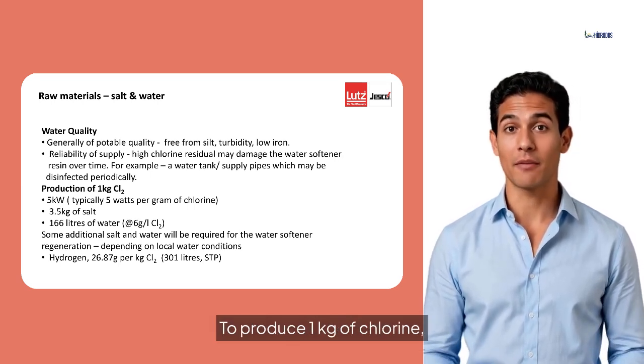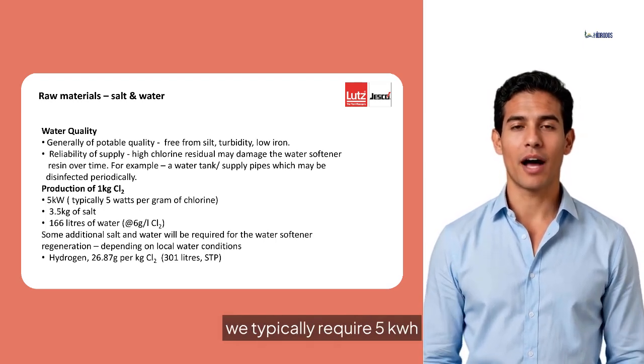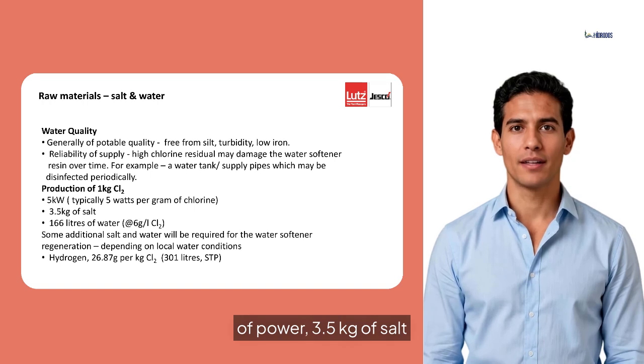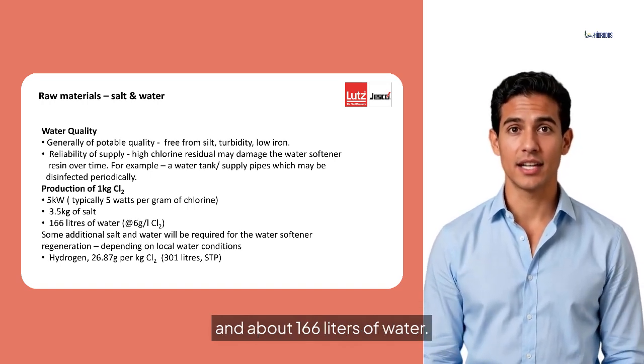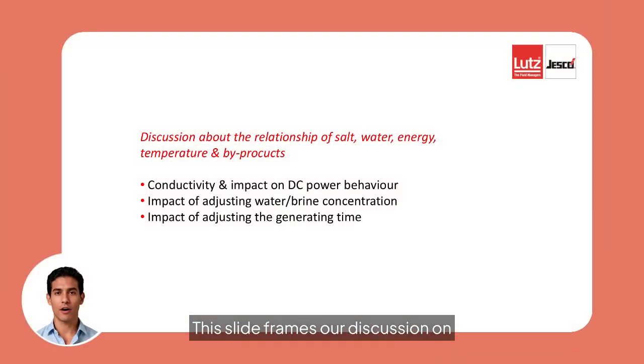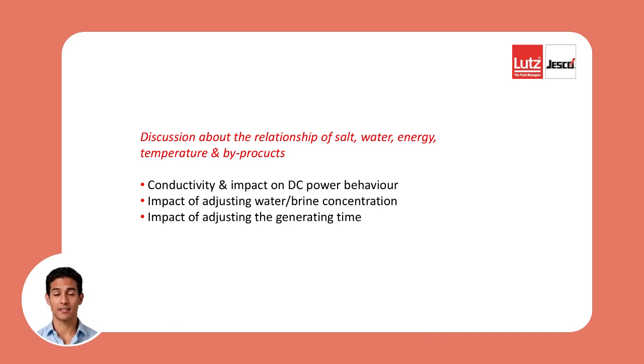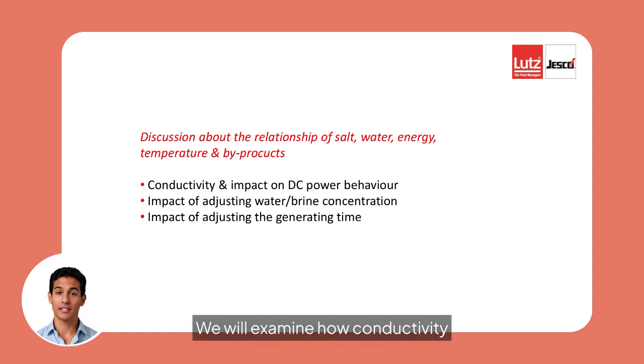To produce 1 kilogram of chlorine, we typically require 5 kilowatt-hours of power, 3.5 kilograms of salt, and about 166 liters of water. This slide frames our discussion on how salt, water, energy, temperature, and byproducts interact. We will examine how conductivity affects DC power behavior, and how adjusting brine concentration or generation time influences efficiency, product strength, and formation of secondary species.